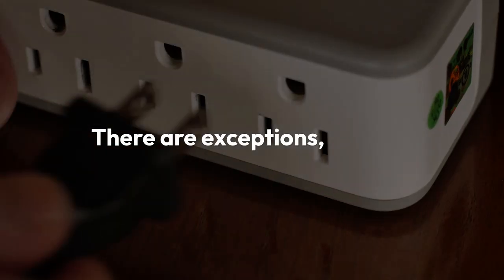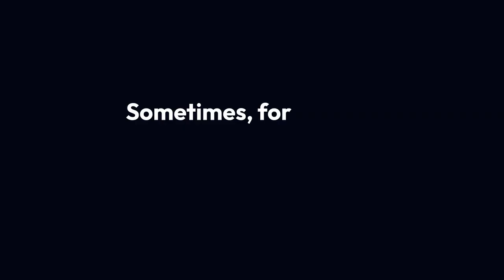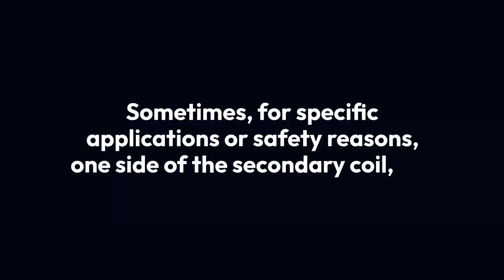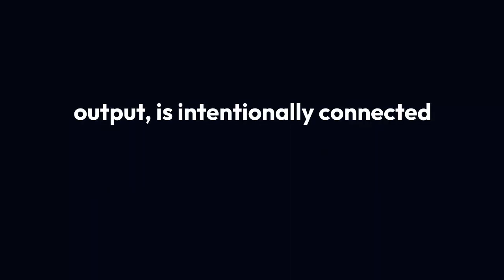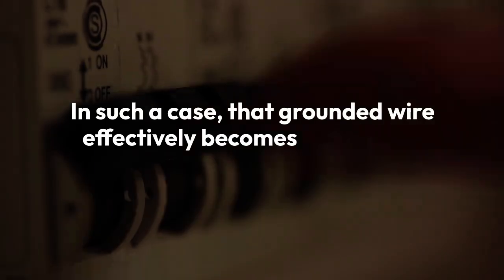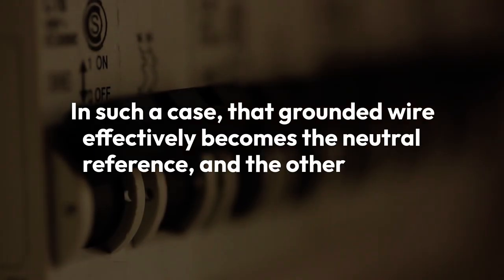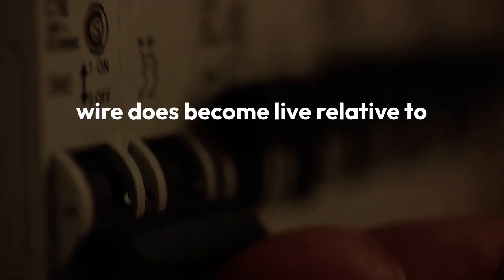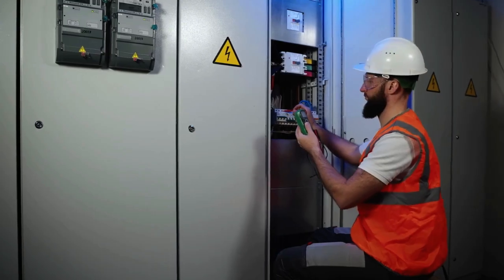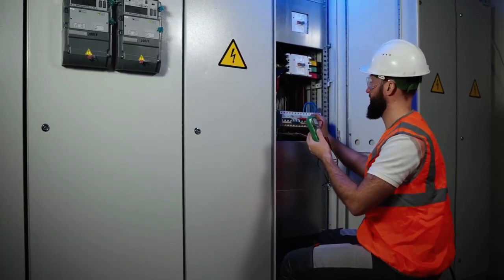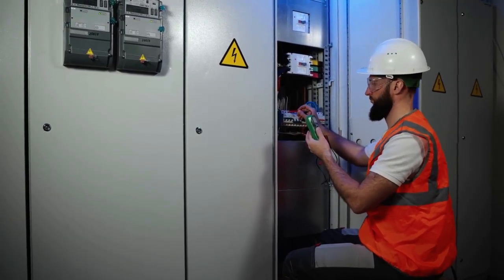There are exceptions, though. Sometimes, for specific applications or safety reasons, one side of the secondary coil, the output, is intentionally connected to ground. In such a case, that grounded wire effectively becomes the neutral reference, and the other output wire does become live relative to ground. But for most common, small AC/AC transformers, you're dealing with a floating output.